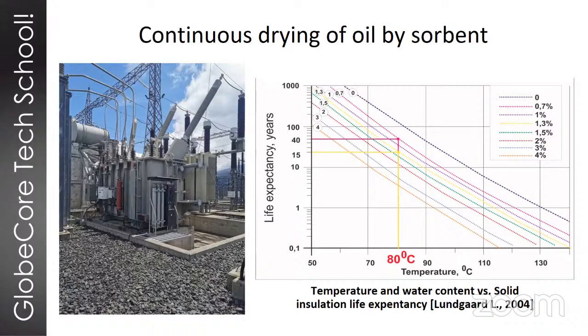So what happens is several columns filled with a sorbent are connected to a transformer, and those sorbents usually have a very high ability to capture water. And then the oil circulates slowly through these cartridges at a low rate, which usually does not exceed something like 30 liters an hour. And at the same time, the sorbent basically extracts water from the oil. And since in a loaded transformer, water constantly migrates from liquid into the solid insulation and then back again, if you have this continuous drying cycle in oil circulation, it also dries the solid insulation, because obviously as you extract water from the oil, the balance shifts, and so more water is released from paper into the oil.